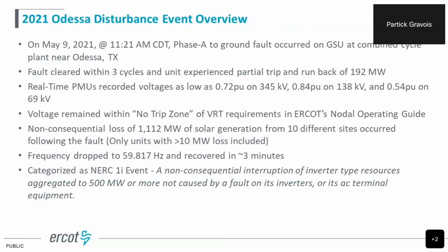We do have about 200 PMUs sending in real-time data throughout the system across ERCOT, many in West Texas as well. From those PMUs, we were able to look at some of the voltages that occurred during the fault conditions. We saw low voltages of about 0.7 on 345 kV, 0.84 on the 138, and 0.5 on the 69. We were able to determine pretty quickly that it occurred on the 345 kV system as well. The voltages we were seeing from the real-time PMUs were all within the no trip zone of the voltage ride-through requirements in both NERC PRC 24 and ERCOT's own nodal operating guides. So right away we were questioning why we had so many resources tripping off due to this normal clearing fault.